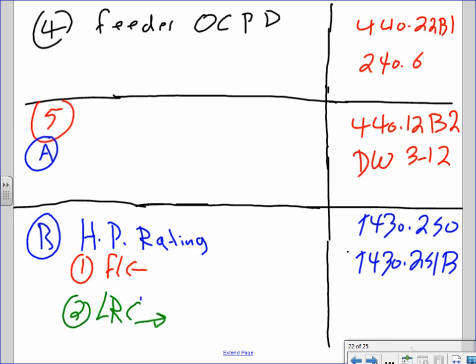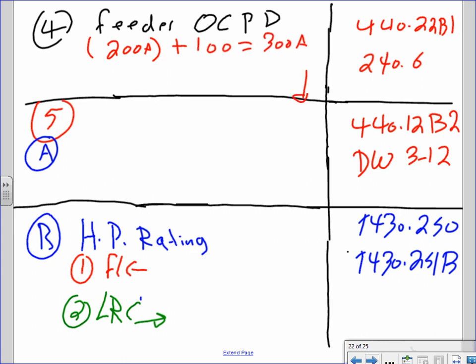Feeder overcurrent protection device: largest individual OCPD is 200 amps plus the full load current of the other motor (100 amps) = 300 amps. Since 300 is a standard size, use a 300-amp fuse.